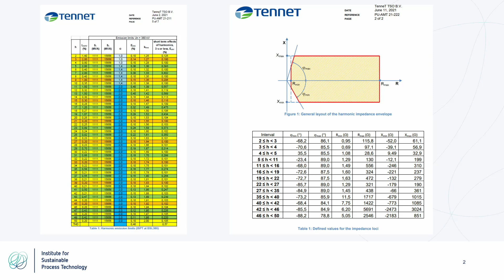On the right-hand side, you see the impedance envelopes. There you see for each and every harmonic, because each and every harmonic can have different impedances, so you need to take care of those during your calculations.